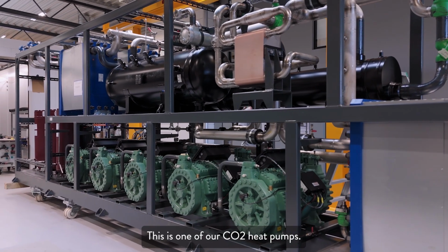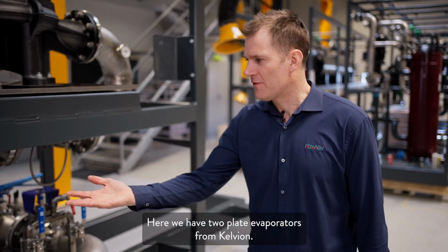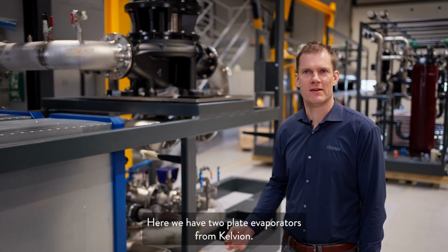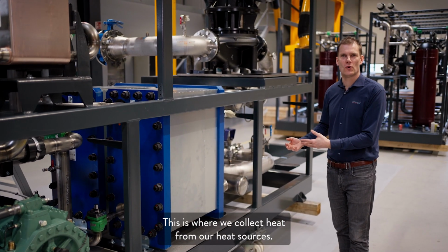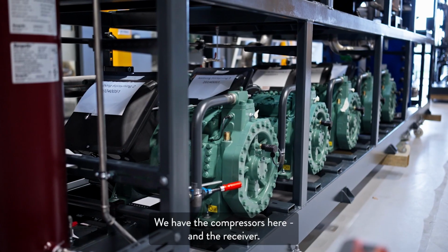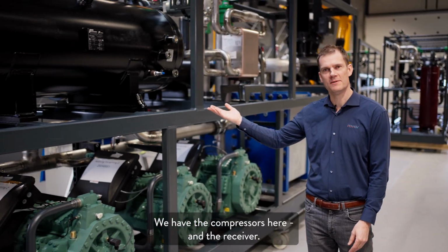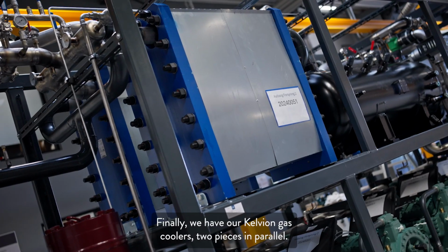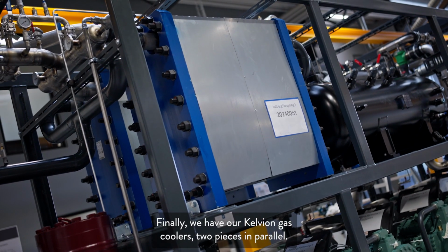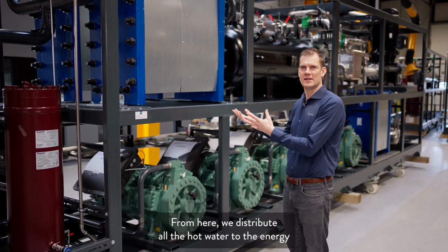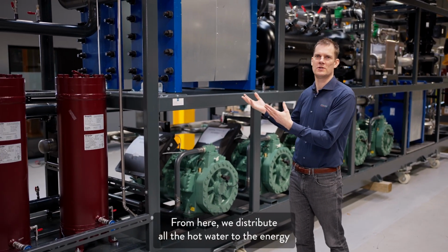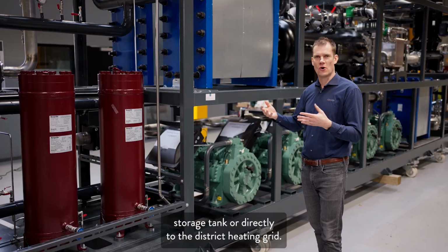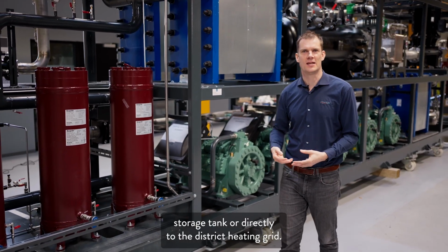This is one of our CO2 heat pumps. Here we have 2 plate evaporators from Kelvion. This is where we collect all heat from our heat sources. Then we have the compressors here, the receiver, and finally here our Kelvion gas coolers, 2 pieces in parallel. And it's from here that we distribute all the hot water to the energy storage tank or directly to the district heating grid.